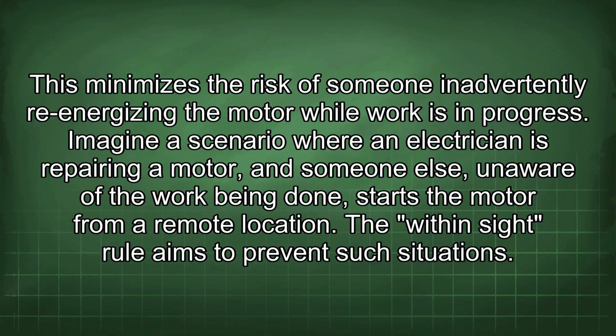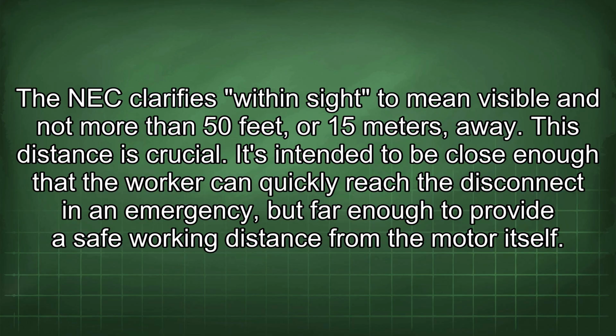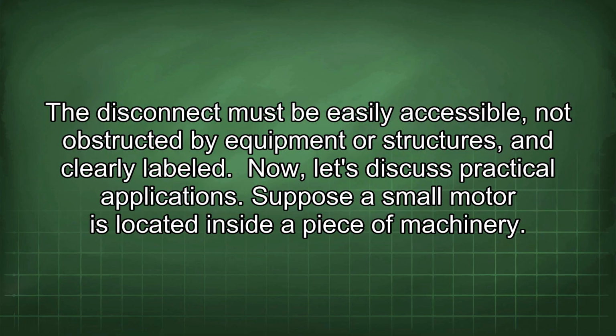Imagine a scenario where an electrician is repairing a motor and someone else, unaware of the work being done, starts the motor from a remote location. The within-sight rule aims to prevent such situations. The NEC clarifies within sight to mean visible and not more than 50 feet or 15 meters away. This distance is crucial. It's intended to be close enough that the worker can quickly reach the disconnect in an emergency, but far enough to provide a safe working distance from the motor itself. The disconnect must be easily accessible, not obstructed by equipment or structures, and clearly labeled.